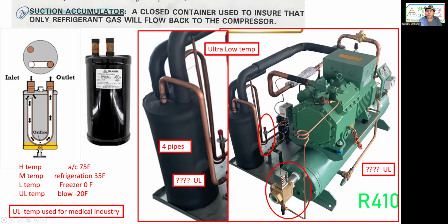If I have to guess, I would say this probably has something to do with temperature because the suction line is so cold. Box temperature below -20 means the boiling point is at -40, maybe -30. The suction line is so cold, causing the liquid line to be cold. In freezers, the liquid line is cold even though the pressure is high, because all the coldness from the low side causes the high side to be cold. What I'm thinking is this is to keep the liquid line warm, so we'll have some kind of subcooling. I don't know much about ultra cold, ultra low temperature. I never worked on it.